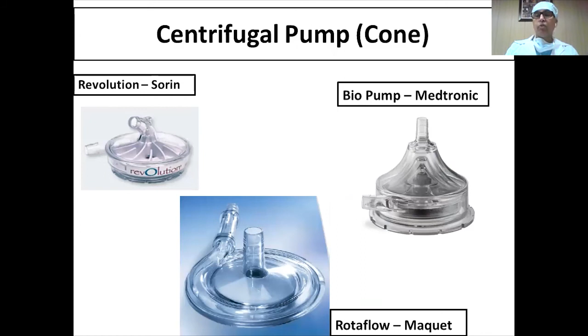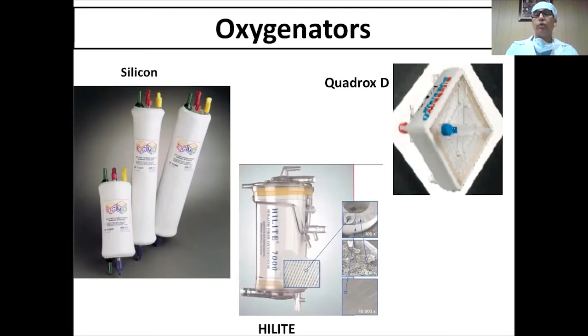These are the oxygenators. These are basically lungs which participate in gas exchange. Here the gas flows inside, and outside the blood flows, so there is no direct contact of the blood and the gas. There is an interface in between. Again, these are made up of polymethylpentene so that they can be kept for 2 to 3 weeks or even sometimes more than that. Otherwise, normal oxygenators can be used for 24 to 36 hours only.